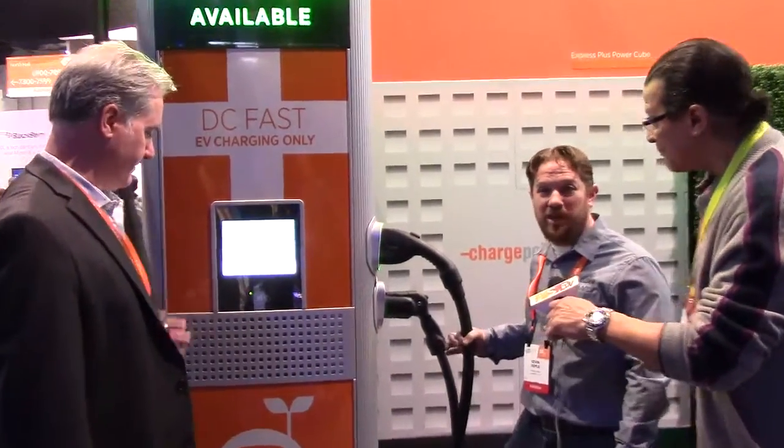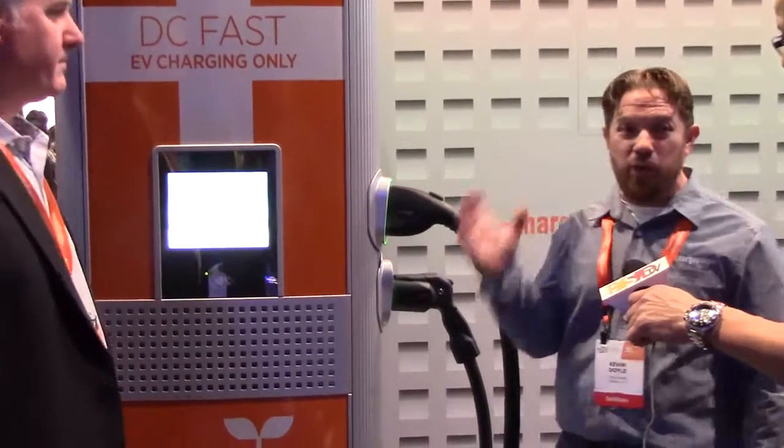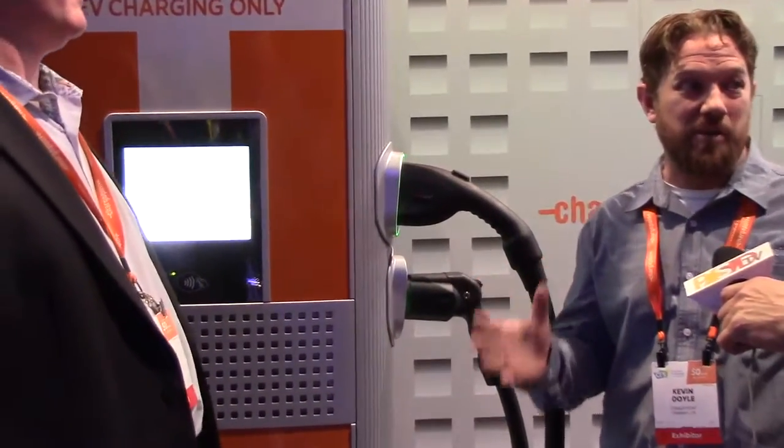Now those are very impressive figures. You're the technical person here, Kevin. Could you tell me a little bit about some of the challenges you had to deal with in getting that? One big challenge is getting 400 amps through a cable that a normal person can actually lift. What we have is liquid-cooled cables, and that allows us to keep a small cable size and push 400 kilowatts of power through that cable.